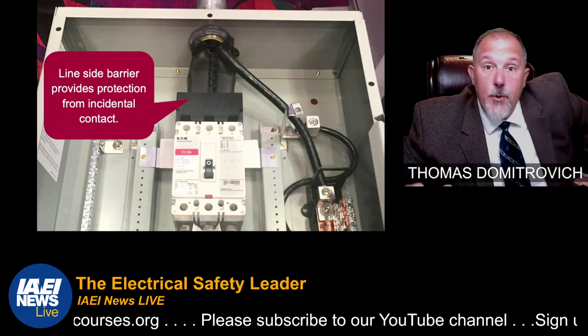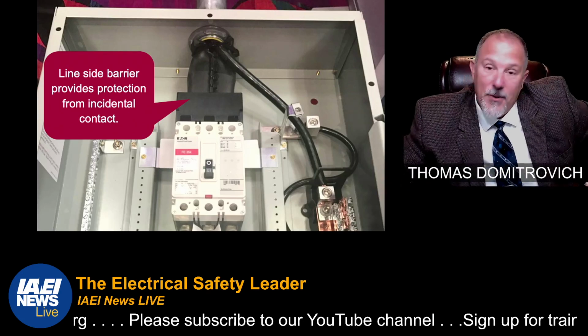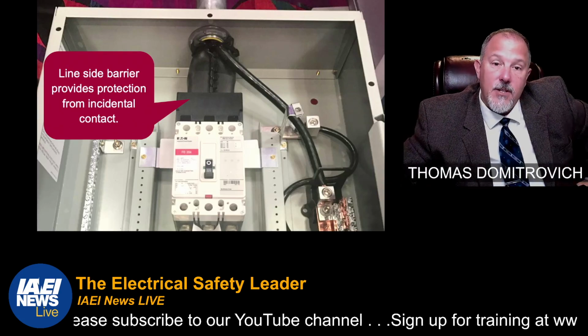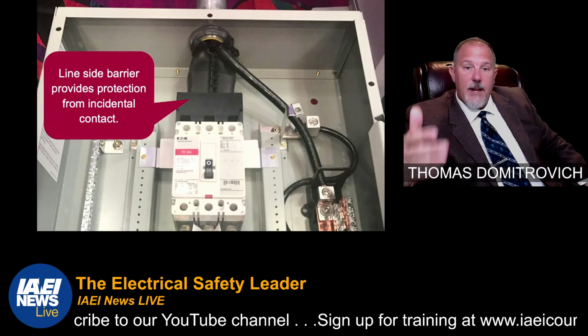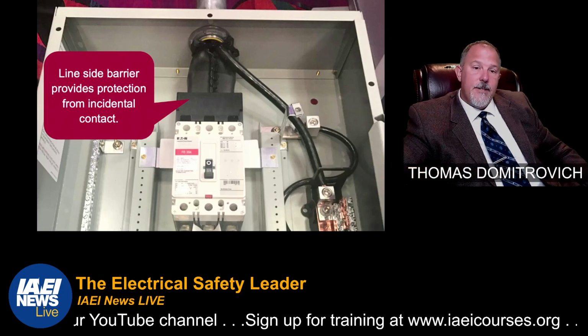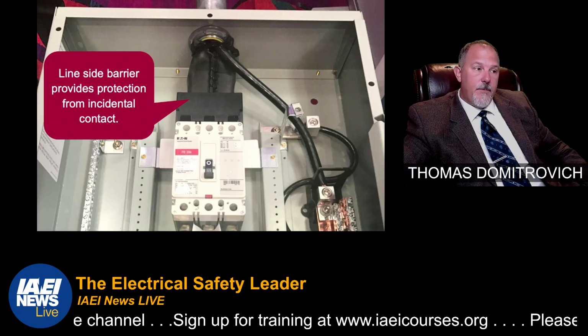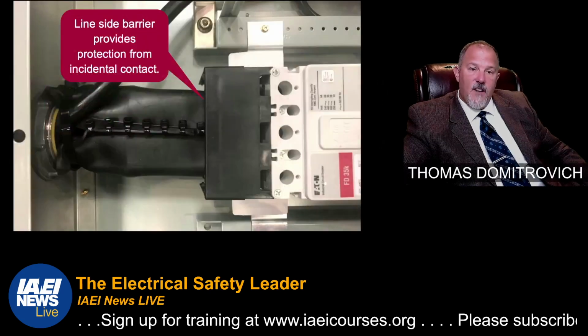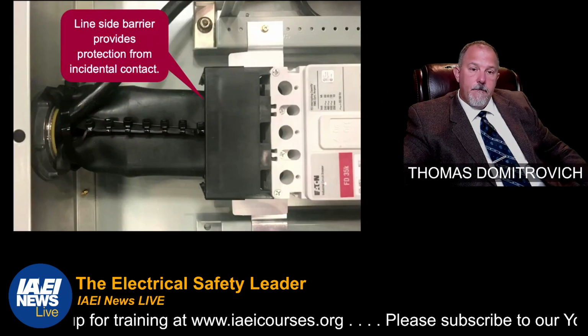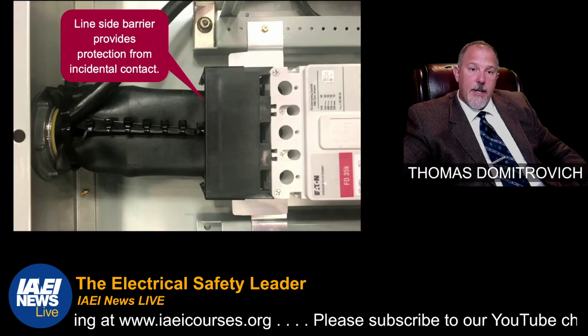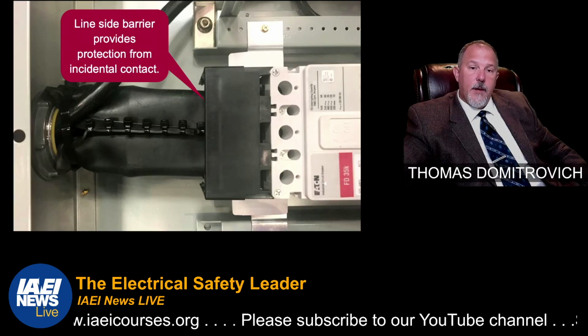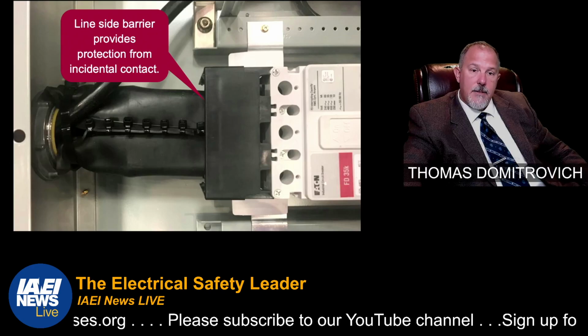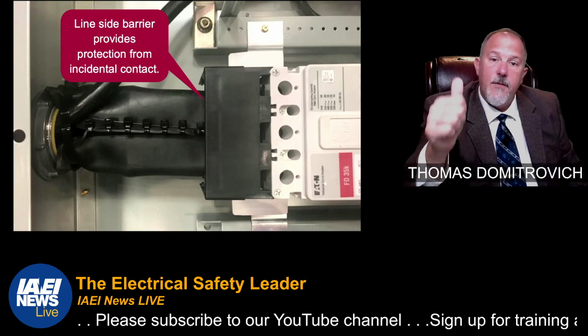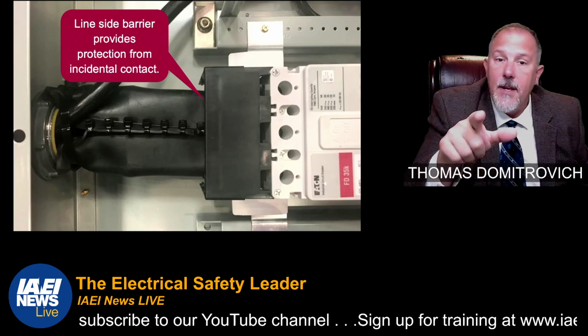I call them booties. Put that around the line side, and that reduces the likelihood of coming in contact with something that's energized when you turn that overcurrent protective device to the off position. That's wrapped pretty tight. It'll prevent incidental contact.